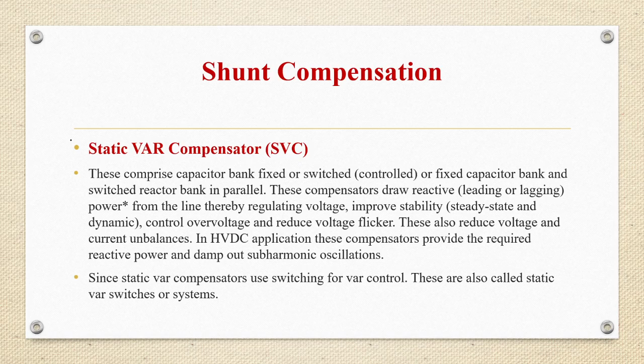These compensators will draw reactive power from the line, thereby regulating voltage and improving stability, both steady state and dynamic stability. They will control overvoltage, reduce voltage flickering, and also reduce voltage and current imbalances. In HVDC applications, these compensators will provide the required reactive power and damp out subharmonic oscillations. Since static VAR compensators use switching for var control, they are also called static VAR switches or systems.